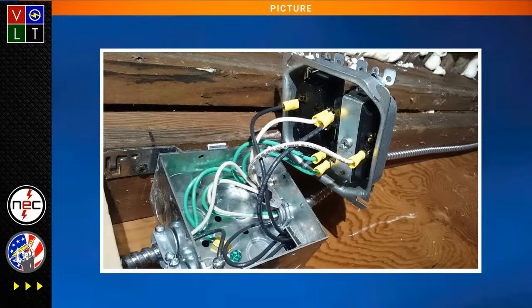So this picture right here is pretty funny. The person that sent it to me didn't want to be mentioned, so I was like, "That's cool. I know how you feel. These guys will probably attack you if they found out who you were." But anyway, this is actually a code violation. These crimp connectors are not listed for solid. It looks like that to be solid. That could be stranded, but to me, that MC cable looks like it's going to be a solid conductor, and typically those crimps are not rated for a solid conductor.